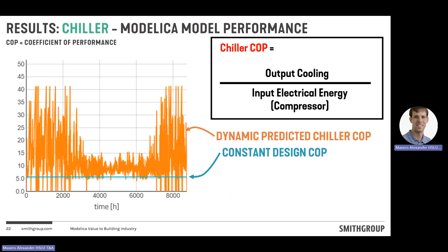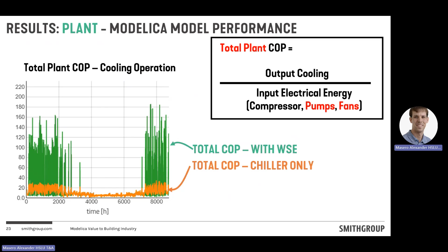So it's the same kind of output cooling from either the heat exchanger or the chiller, but now we added the pumps and the fan. So what's running in the system to get a system COP? Before, we showed the design COP constant, and it was dwarfed by the part load chiller. Now the chiller's dwarfed by, when the compressor's off, you're just running a pump and a fan. We're getting over 100 COP.